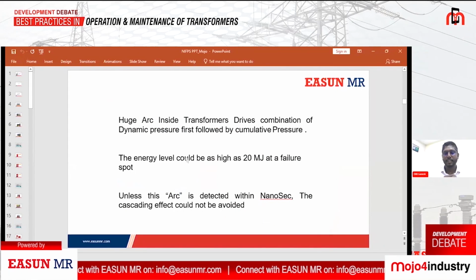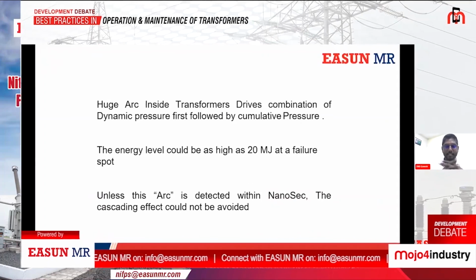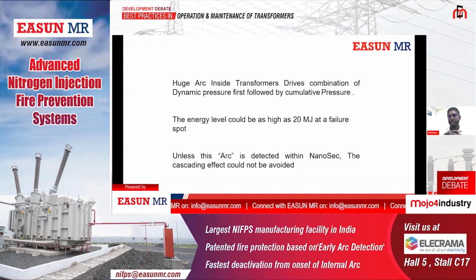See, our NIFA system working is based on the arc relay, an arc-sensing based system, which is the quickest system in India, which we patented in the year 2015. The existing systems available in India take up to 180 to 200 milliseconds to operate a nitrogen system when they receive the command from the transformer protection relays.